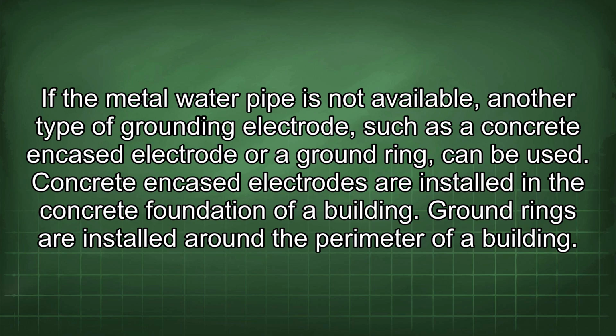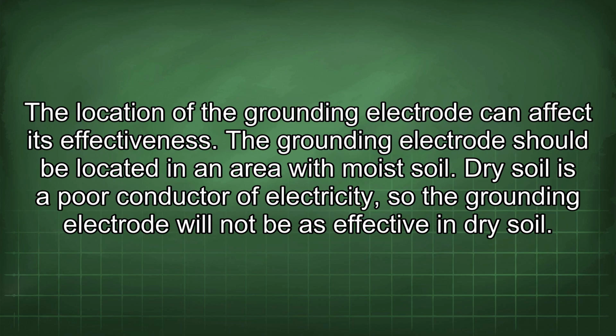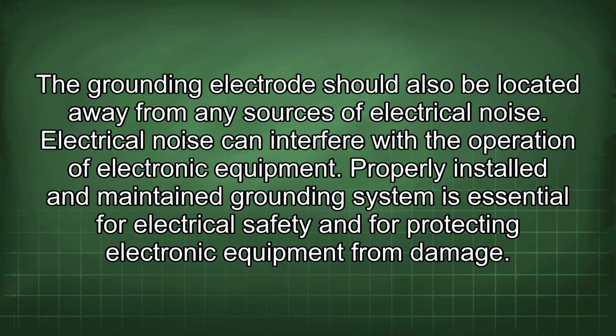Concrete encased electrodes are installed in the concrete foundation of a building. Ground rings are installed around the perimeter of a building. The location of the grounding electrode can affect its effectiveness. The grounding electrode should be located in an area with moist soil. Dry soil is a poor conductor of electricity, so the grounding electrode will not be as effective in dry soil. The grounding electrode should also be located away from any sources of electrical noise. Electrical noise can interfere with the operation of electronic equipment. A properly installed and maintained grounding system is essential for electrical safety and for protecting electronic equipment from damage.